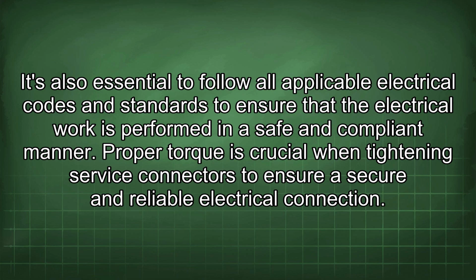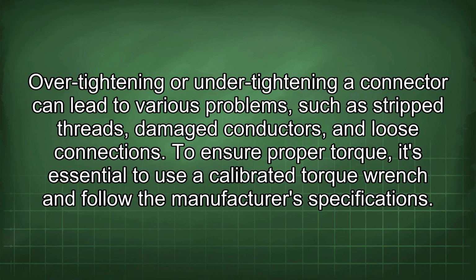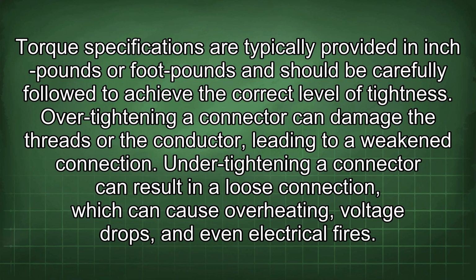Proper torque is crucial when tightening service connectors to ensure a secure and reliable electrical connection. Over-tightening or under-tightening a connector can lead to various problems, such as stripped threads, damaged conductors, and loose connections. To ensure proper torque, it's essential to use a calibrated torque wrench and follow the manufacturer's specifications. Torque specifications are typically provided in inch-pounds or foot-pounds and should be carefully followed to achieve the correct level of tightness. Over-tightening a connector can damage the threads or the conductor, leading to a weakened connection. Under-tightening a connector can result in a loose connection, which can cause overheating, voltage drops, and even electrical fires.